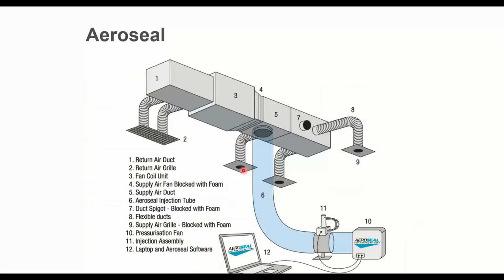So we're going to block off all these intentional diffusers, because we don't want to seal those shut, because that would be stupid, because we want air to actually move through there someday. So we're going to seal off all the intentional openings, and then we're going to cut a hole in the duct somewhere, and we're going to connect this bag to it. And that bag is connected to a fan system.